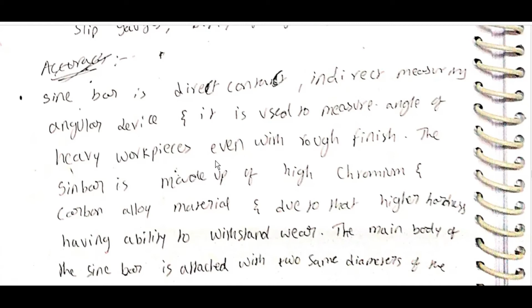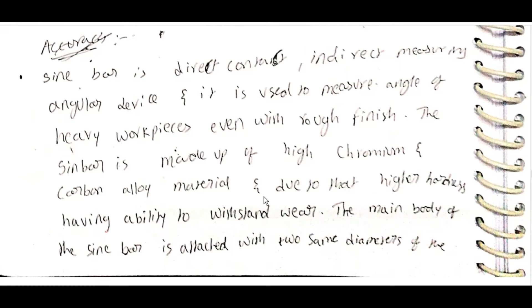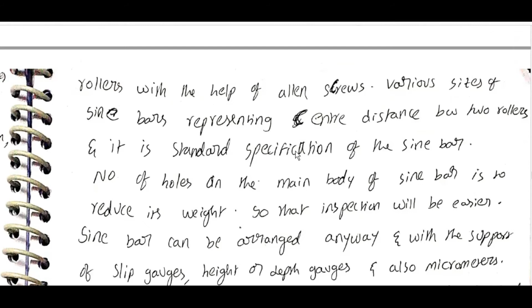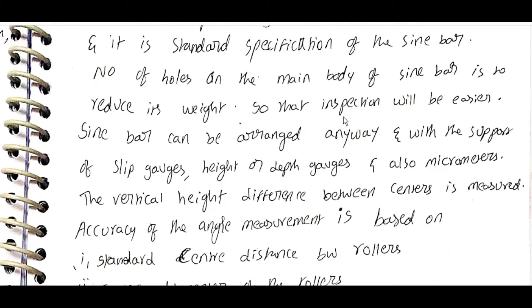even with rough finish. The sine bar is made of high chromium and high carbon alloy material. Due to its higher hardness and ability to withstand wear, the main body of the sine bar is attached with two rollers of the same diameter with the help of Allen screws. Various sizes of sine bars represent the center distance between the two rollers, and it is the standard specification of a sine bar. The number of holes on the main body of the sine bar is to reduce its weight so that inspection will be easier. The sine bar can be arranged any way, with the support of slip gauges, height or depth gauges, and also a micrometer. The vertical height difference between centers is measured.